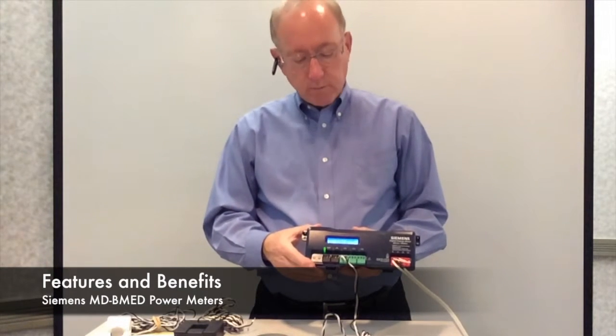The MD-BMED series meter is highly competitive in the marketplace. One of the key advantages of this meter is that it provides up to 80 electrical parameter measurements within the BACnet or Modbus registers. This is significantly more than many other meters of its type in the industry. Also, the flexibility of the meter with the capability of putting various CTs onto these ports does not lock you into having the meter and the CT together. So flexibility in the future for changes or reapplication of this device to other types of equipment is not only possible but easy to do.